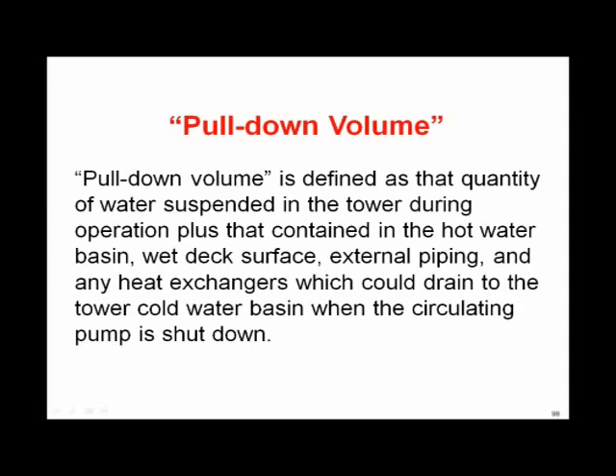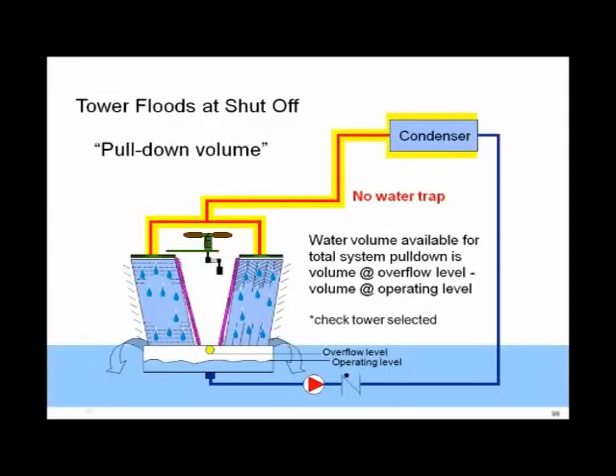What would cause a tower to overflow? Well, if you pipe a tower like this, you're going to get overflow. In other words, take a look. This tower is designed for pull down volume, but not for the water in all the overhead piping, not for the water in the condenser, not for the condenser piping. And all that piping is above the tower. So in this case, when you turn the pump off, all the water in the condenser and the condenser water piping does what? There's no water trap.